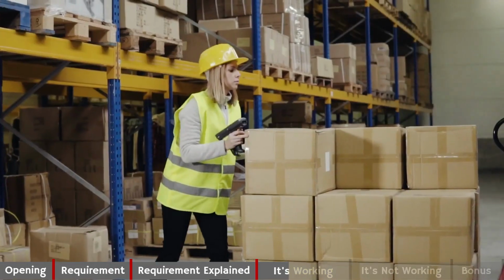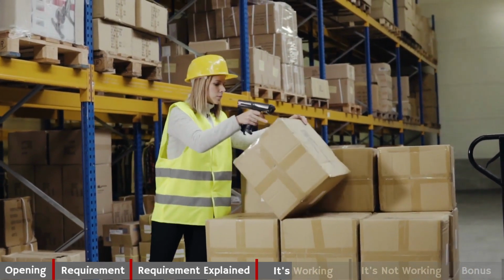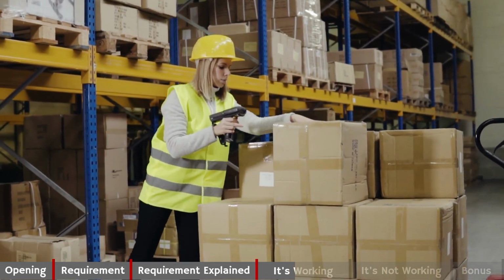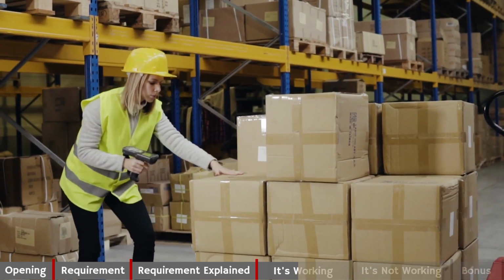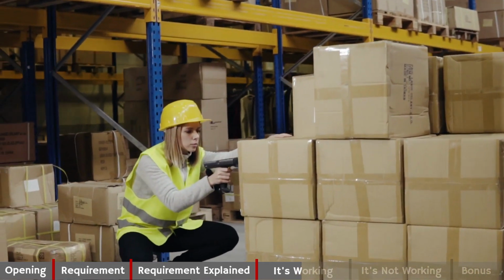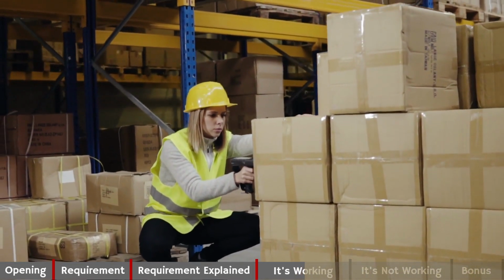So how do I know this is working? Well, first, I fully analyzed with risk management all the risks that may be presented to my product during manufacturing, handling, storage, shipping, distribution, and installation. And I've implemented appropriate controls to prevent damage. Second, I've done all the needed testing, shake, rattle, and roll, stability, whatever it is. I've done the testing to show that my packaging is good and it protects my product.